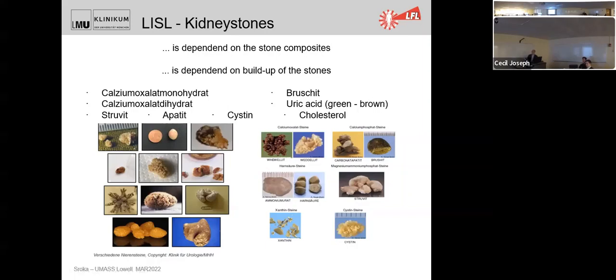Unfortunately, this kind of stone and this kind of stone and this kind of stone cannot be destroyed with these kinds of lasers. So then they came up with the idea that in every stone there is some water. And if we use the water as the target, which we want to excite or vaporize so that there is tension on the stone, then all stones can be covered. And therefore, the medical doctors, or specialists in development, started from the visible laser systems up to the infrared laser systems. And nowadays, the Holmium laser is the workhorse.